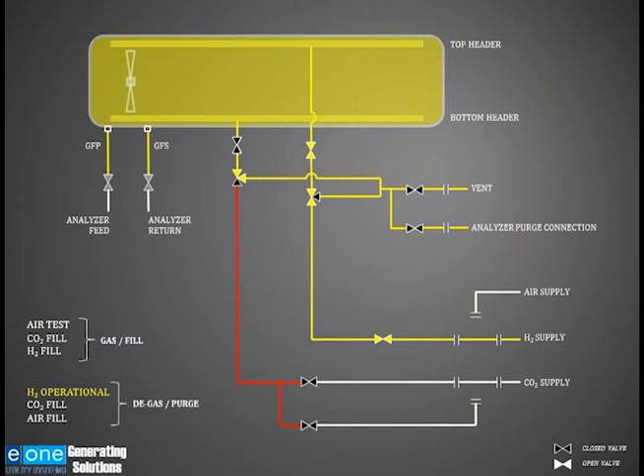Now that the generator has been filled with hydrogen, I can go into my normal operation, opening the valves to the analyzer. The fan's now turning. I've got a differential pressure that's going to create a flow through my gas analyzer. You'll note that the hydrogen supply is still tied to the generator, and there will be a regulating valve there that will keep that generator pressure at a predetermined point, typically 30 or 60 psig. I'm not going to go through the CO2 fill or the air fill, which is a degassing process. This is just a reverse of what we did previously.